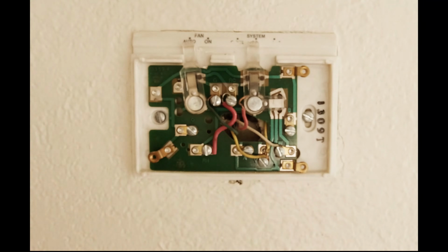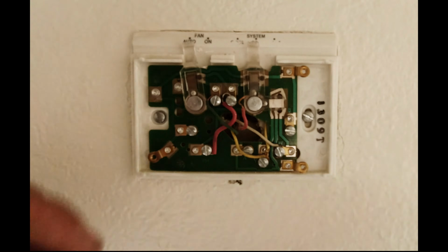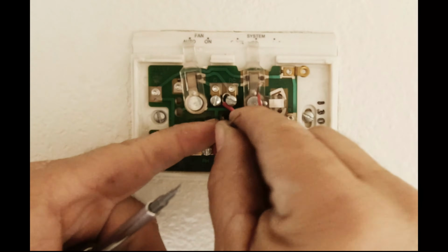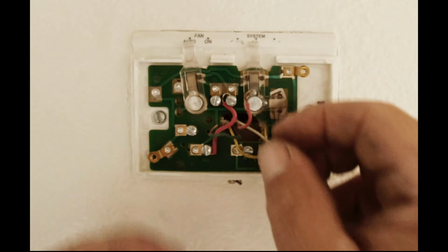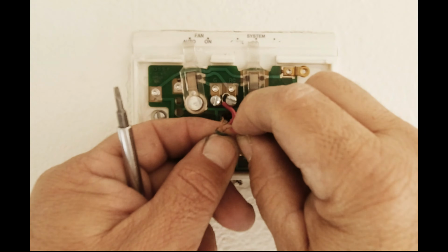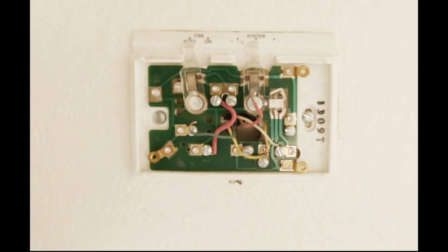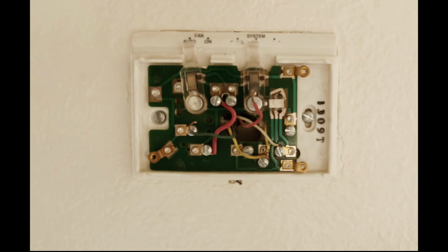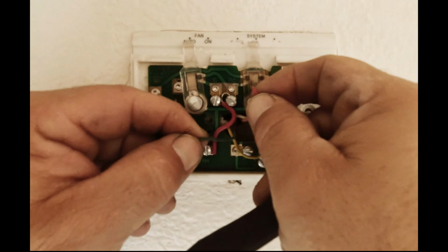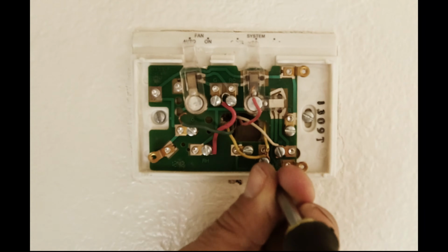But if your thermostat has a battery in it, then it probably doesn't have the C terminal connected. Now the red wire, or whatever's connected to the R, is always going to be the 24 volts. The green is always going to be marked G, and that's the fan. Now, if you connect the 24 volts over to the fan and you hear that fan kick on, then you know that's good. There's nothing wrong with the fan. If it doesn't kick on, it could be a capacitor on the fan, it could be a tripped breaker, or even a burnt breaker.